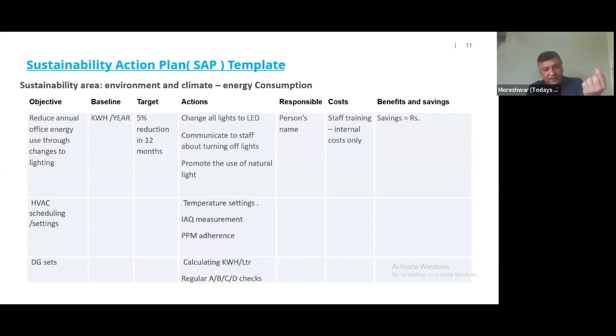HVAC settings, a 1 degree reduction can save a lot of energy without affecting internal air quality. One example: in winter, when the outside temperature was around 16 degrees, one brilliant engineer opened the fresh air intake completely to 100%, stopped the compressor chiller, and just ran the air handling unit to circulate the cold air available in the atmosphere inside the unit. This small action meant the chiller was off for 3 hours, saving a lot of energy in chiller running.